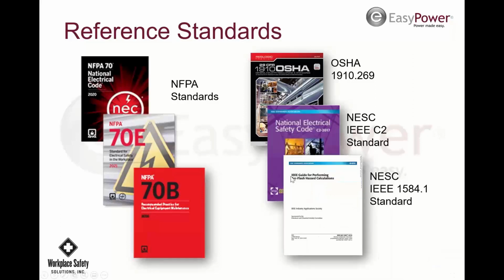Then there's the IEEE 1584 standard, which is used for arc flash analysis. That was updated in 2018. That's why we asked whether you've done the arc flash study in the last 3 years, because the new standard came out in 2018 and was actually available, I think, in 2019. That changed things. It went from 6 formulas to 66 formulas, so it's a lot more comprehensive than it was. It does require more data to be collected on the type of switchgear you have and so forth, but it's a really good way to go. You probably want to update that when you can. Don't go more than 5 years; if you had it done in 2016 or 2017, that would be 5 years now anyway. So that will change things a little bit.